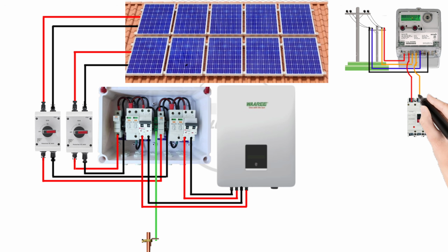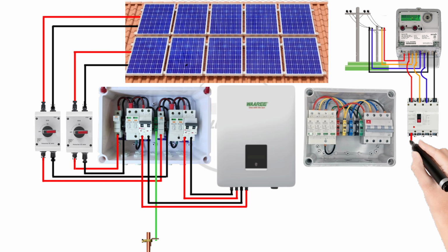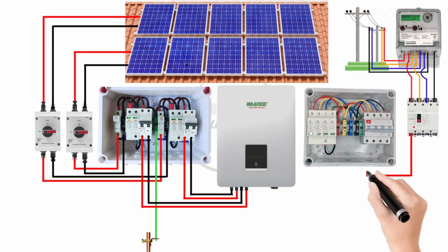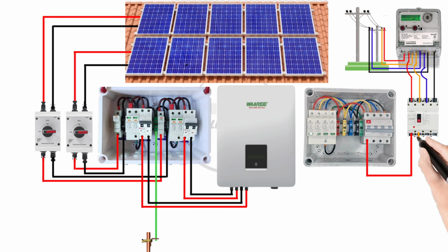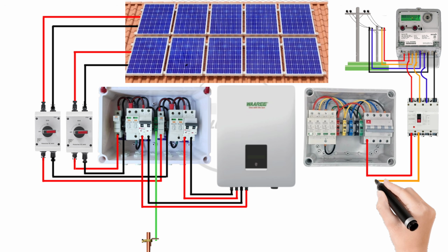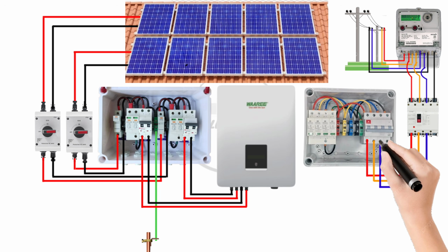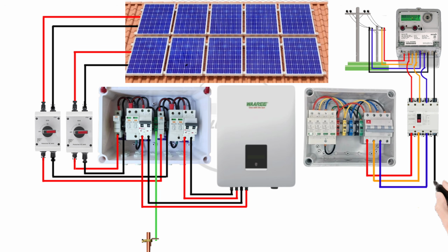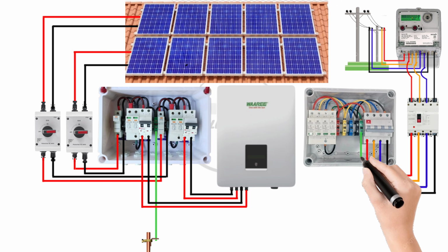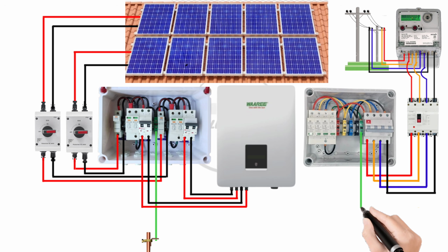It's crucial to match the phase correctly. The energy meter measures the electricity consumed. The output of the energy meter then goes to the input of our 4-pole AC disconnect switch. This switch allows us to isolate the solar system from the grid for maintenance or emergencies. Then connect the terminal from the AC disconnect switch to the 3-phase MCB. The MCB provides overcurrent protection, preventing damage from short circuit or overload. Make sure the MCB is rated appropriately for your 5 kW system. Then the SPD is connected parallel to the input of the 3-phase MCB, or miniature circuit breaker. The SPD protects the system from voltage surges caused by lightning strikes or other electrical disturbances. The ground wire should be connected to the designated ground terminal on the SPD.